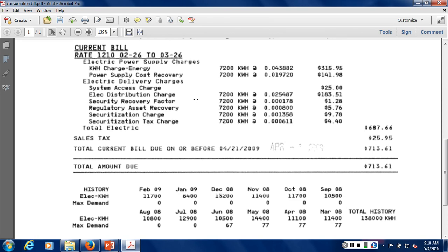Now if you remember, we talked about five different billing charges in a consumption bill. How do I know it's a consumption bill? All I have to do is look at the units column — every unit is KWH. The only level bill that has only KWH is a pure consumption-based bill. It should have the five categories we talked about. Somewhere on here there should be a customer charge — on this bill it's called a system access charge. It's not based on the quantity of energy used; it's just a flat rate of $25 a month, and this would be the minimal charge the customer gets billed no matter what.